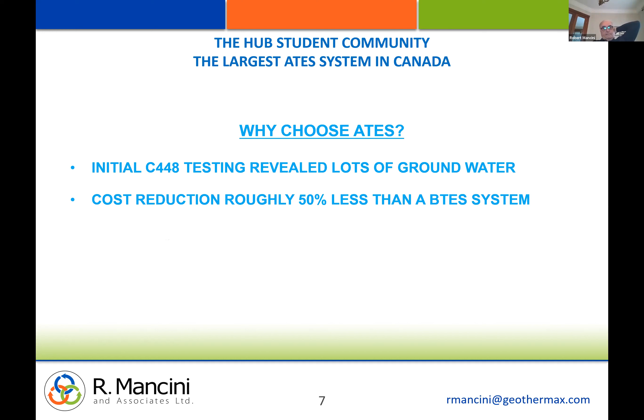Basically, this is a typical ATES system. We have a supply well system, typically with submersible pumps, and sediment separators that pull out things like sand - these are typically centrifugal type units that remove sand and anything that comes through the system. Then we have a plate frame heat exchanger to separate the groundwater system from the heat pump system in the building. The reason for that is that typically water will not be as clean as you might think - there are lots of chemicals and so forth, so we don't want that to foul the heat pump units.